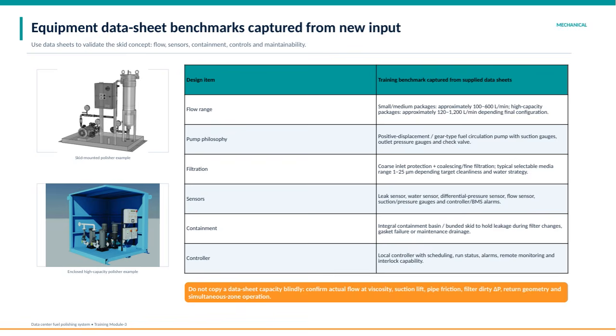One important caution is not to accept datasheet capacities at face value. Always validate actual flow considering factors like viscosity, suction lift, pipe friction, dirty filter differential pressure, return geometry, and whether multiple zones operate simultaneously. This ensures the system performs as expected in real-world conditions.